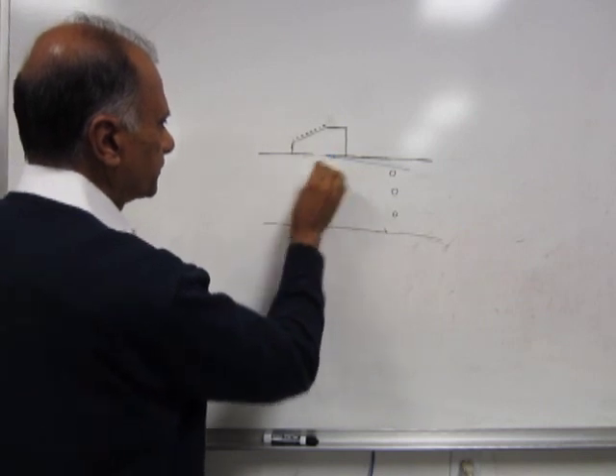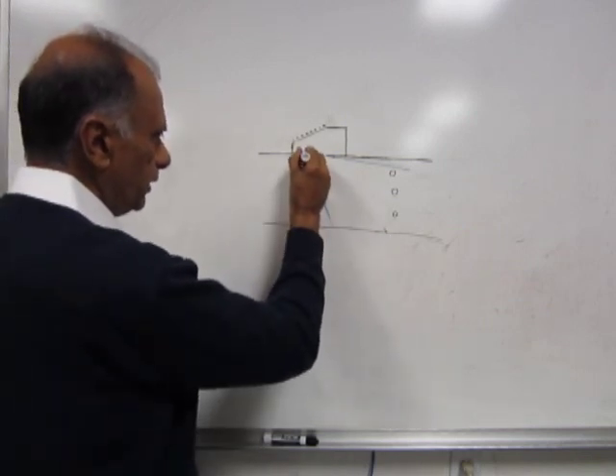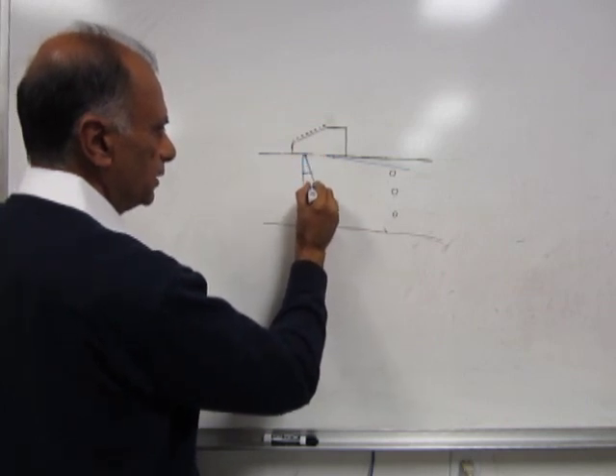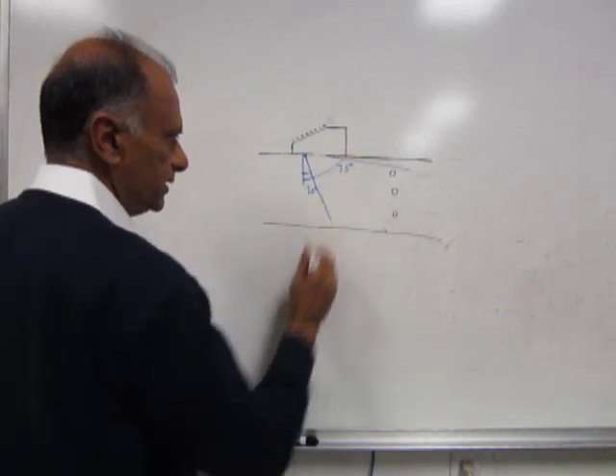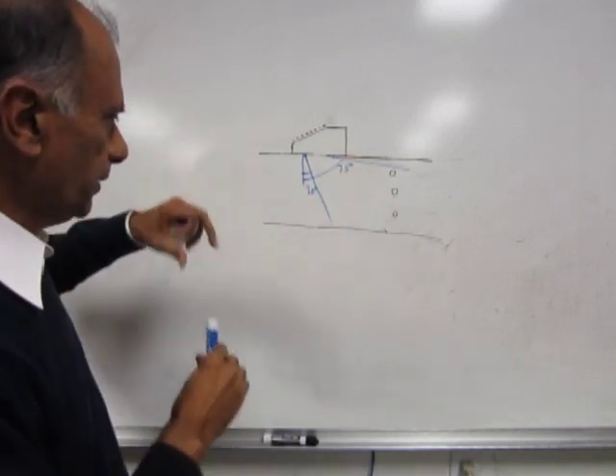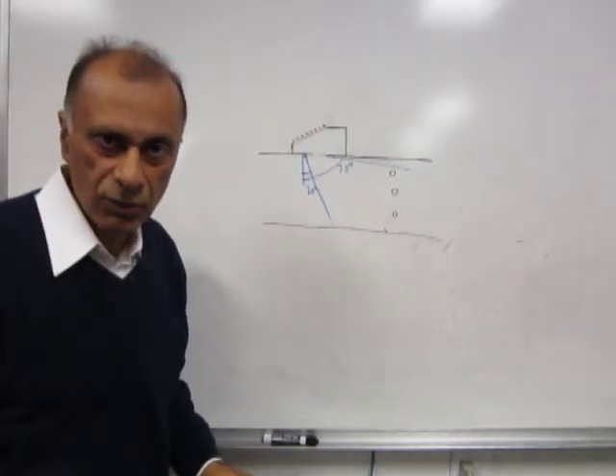And it would mean that I can control the beam from for example 30 degrees to a refracted angle of 75 degrees. So when we sweep the beam like this from 30 to 75, we can actually see all the three holes.